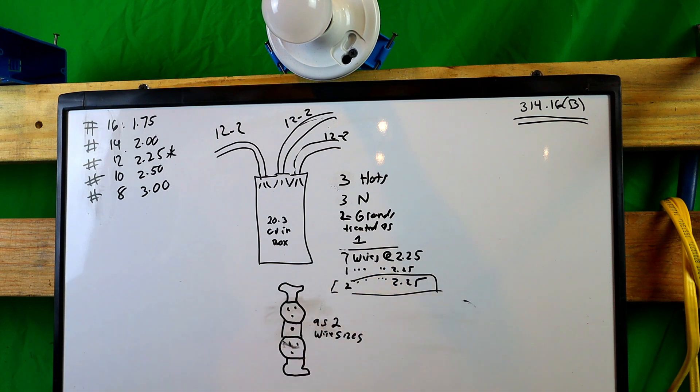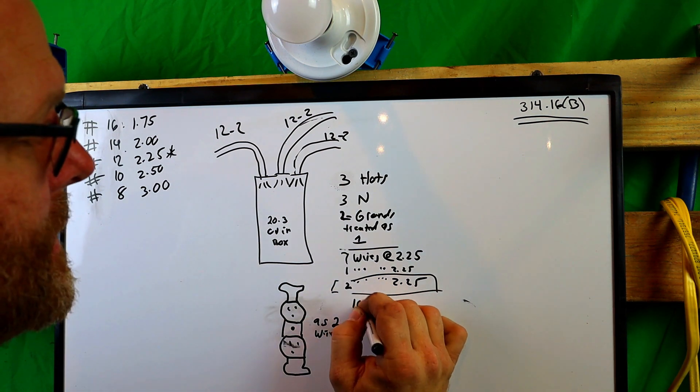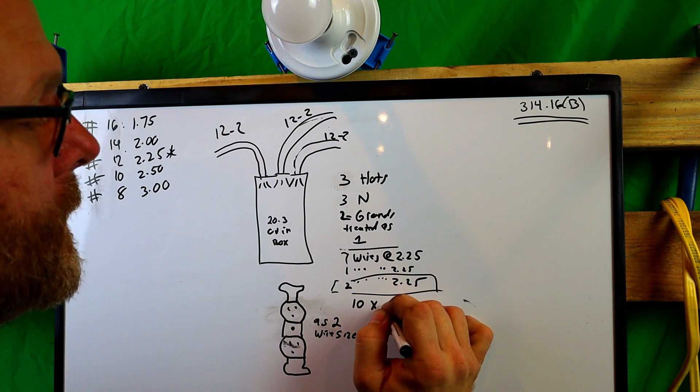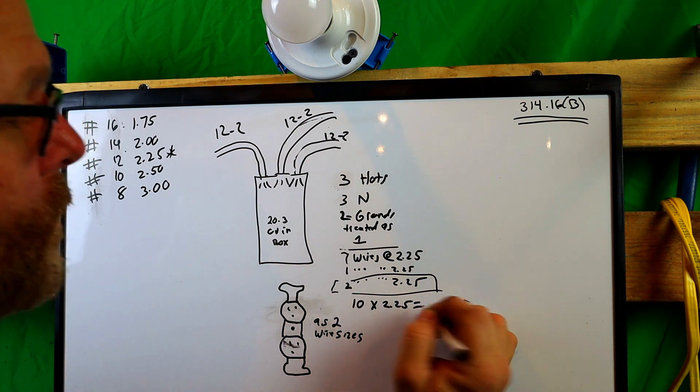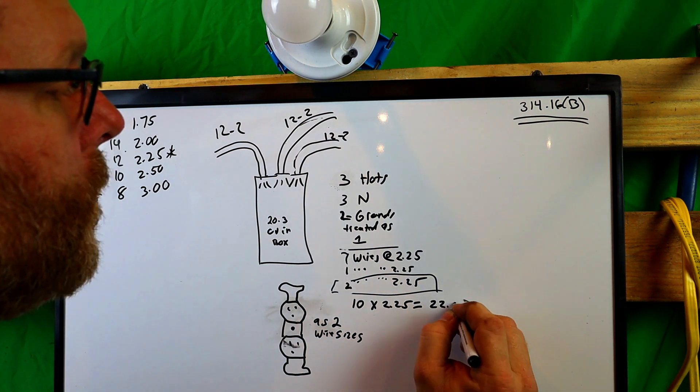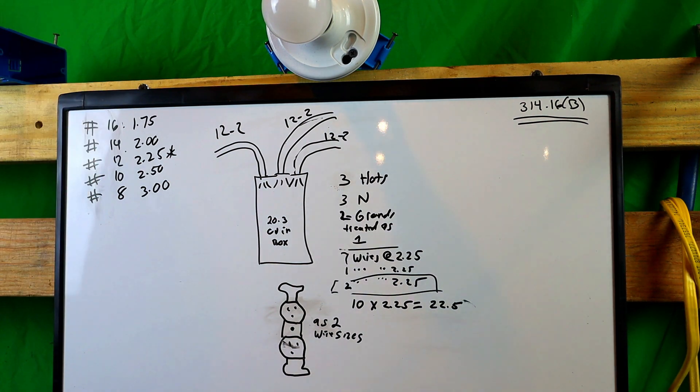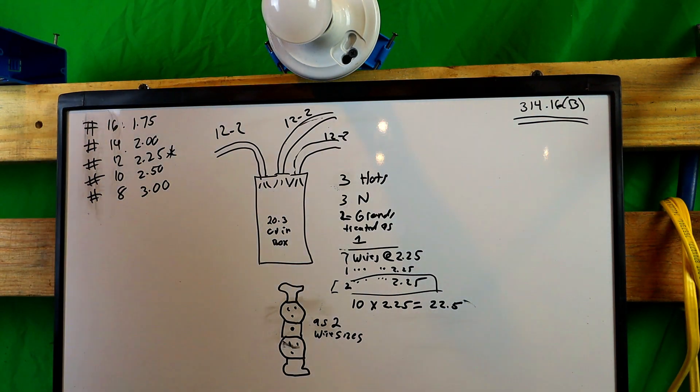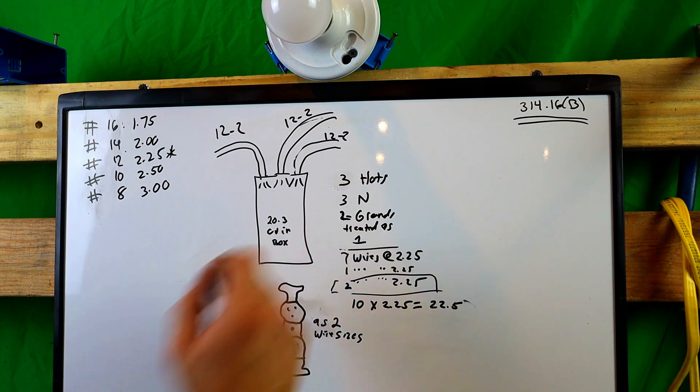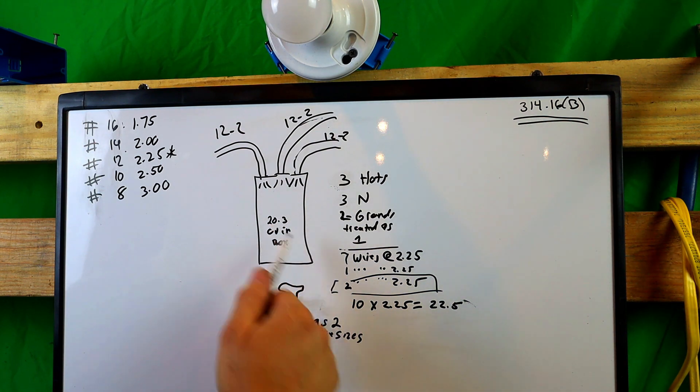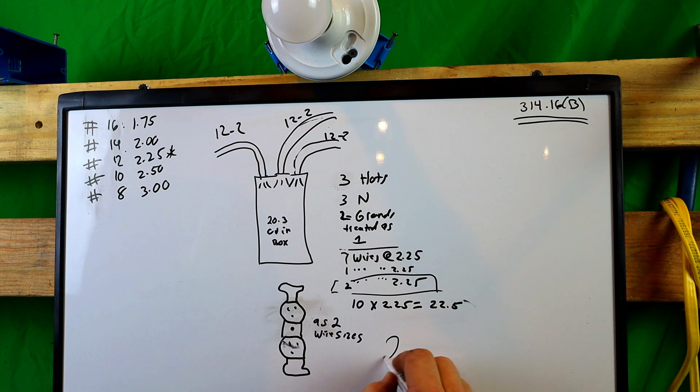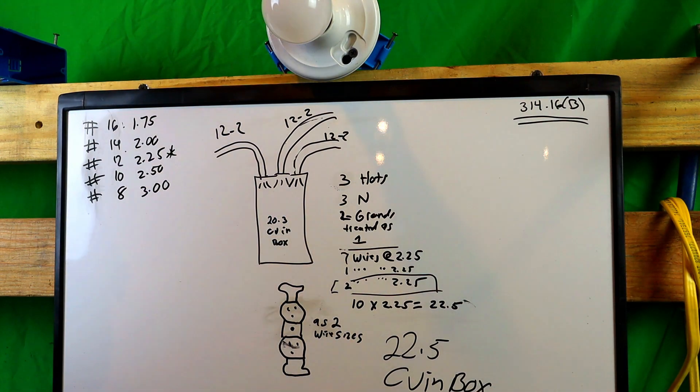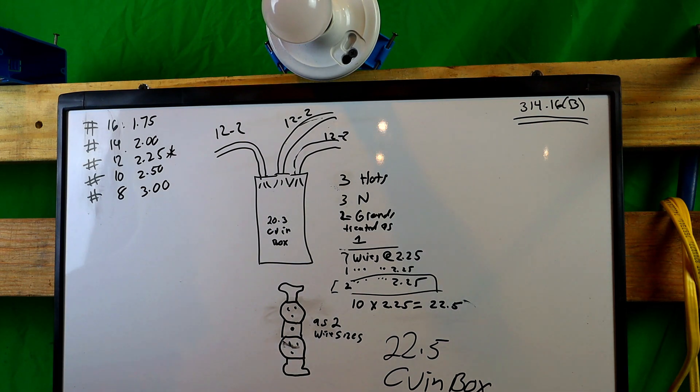So we have ten times 2.25, and that equals 22.5. Now what happens here? We're in trouble because this box here is not big enough. We need a 22.5 cubic inch box. Could you put those wires in there? Absolutely. We know we could. By code, can you? No.